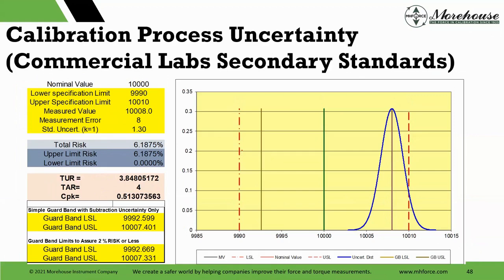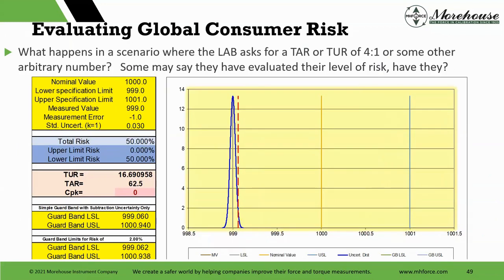Now everything goes up. That same instrument, same measurement at 10,008 that we called good, if we switch to a secondary standard, we switch to a calibrating machine. The dead weight machines are busy all day. We don't do that. If we say on our quotes, if it's dead weight and you get dead weight, but if we did, the risk would go up. We couldn't make a conformity assessment, right? Depending. If you sent us a contract that said, hey, we need our total risk to be less than 10%, we could make it. If you said we need to be less than 6.2, we could make it. Most people are going to say 2.5 or 2%. They're going to go by the standard.